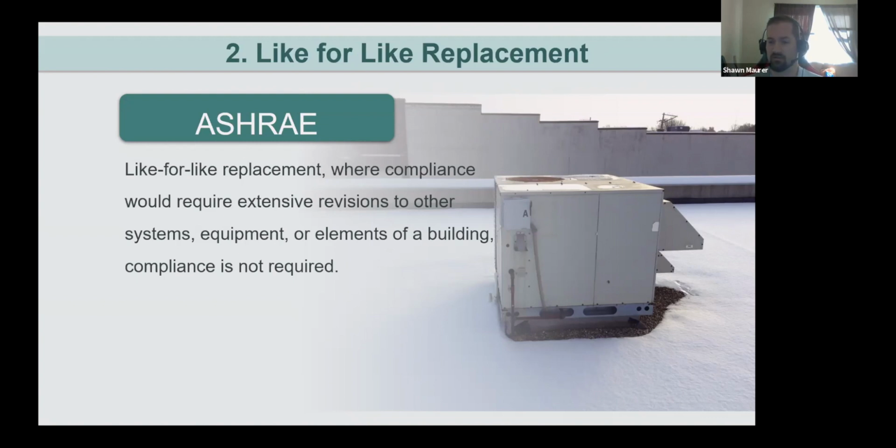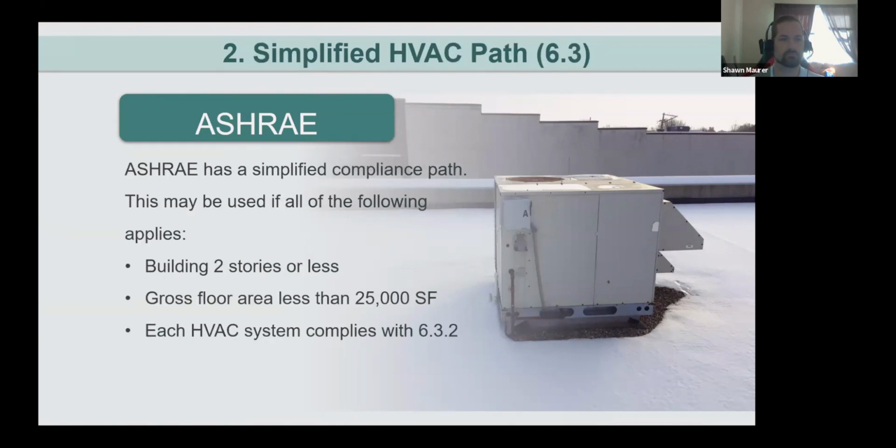And then you don't need to do a full explanation on why the full compliance isn't practical and try to get some waivers for that compliance path. And you're also likely to reduce the cost of that replacement. Downsizing that equipment is going to decrease that capital cost, which may mitigate the additional cost to do that additional load sizing calculation to begin with. So something to be aware of when looking at ASHRAE, that it does have this particular exception in limited cases that is not included in the IECC.